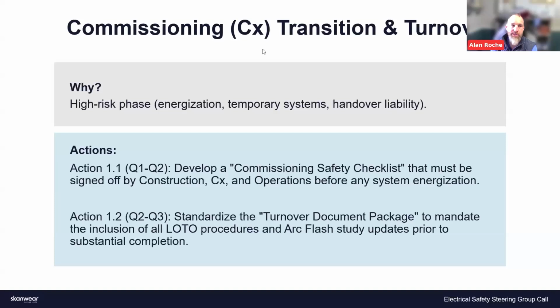I definitely push for operations to make sure they get all their screenshots during commissioning, because even getting up to 50% load in the building might take a year. So grab those screenshots and pictures of what the equipment looks like beforehand. We push for operations to be there for every pre-energization inspection, because they're the ones who own it and define whether it meets the standard.